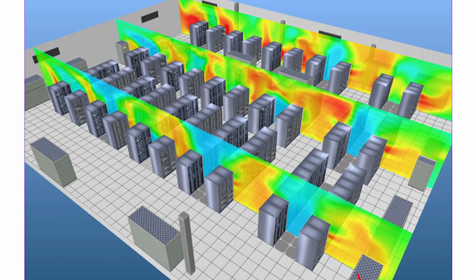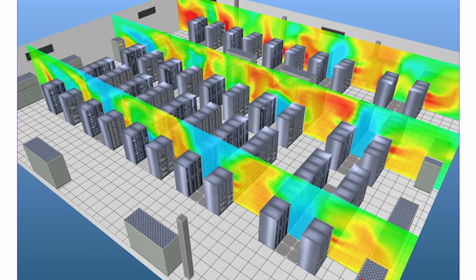Data center CFD models that increase operating temperatures are growing. Forget your classic 68 to 72 degrees Fahrenheit, 50% relative humidity. I want to have at least an 80-degree inlet temperature with a delta T of 25 degrees. Why not? It's energy efficient.